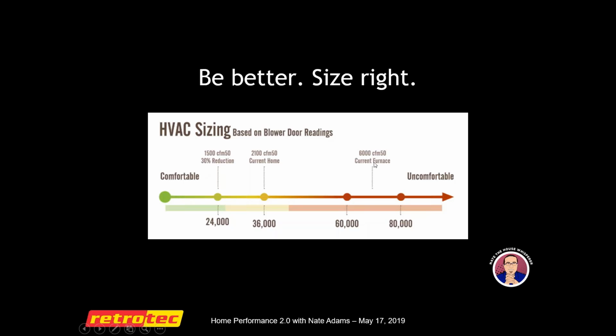Meanwhile, what the house actually has is a 70,000 BTU furnace. And to make that actually correctly sized at 5 degrees, which is the design temperature there, you have to triple the leakage of that house.